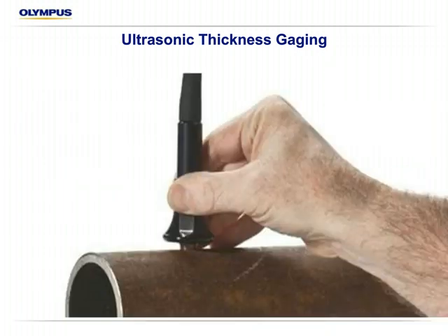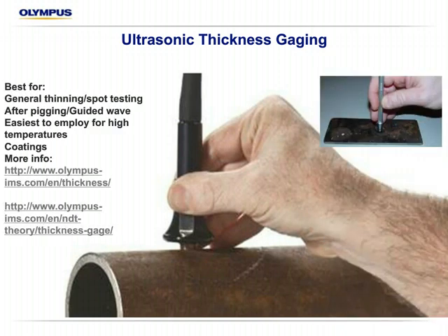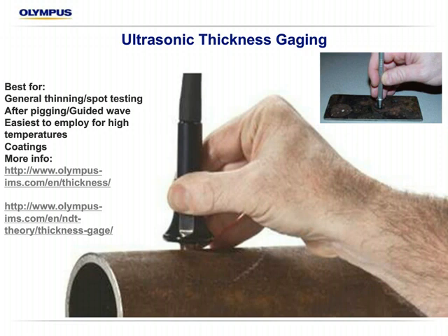Just a mock-up of dual element on a pipe, looking in that case mainly for internal corrosion. And if we were looking for external corrosion, or we could visibly see external corrosion, we have special small point sonopens and other things that can go down into the pit and measure the remaining wall as well. So the basic concept is the same either way.